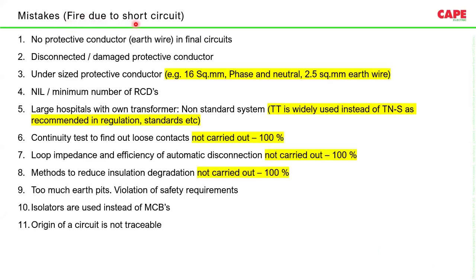Now, from the survey, the general findings we see are these. In a lot of cases there is no protective conductor, no earth wire in the final circuit. In the final circuit, in the sense, in the medical location, there are sockets available, but there is no earth wire on the socket. Most often the protective conductors are disconnected or damaged. Number 3 is an undersized protective conductor. That means the phase and neutral are 16 square mm, but the earth wire is only 2.5 square mm. This is actually a violation. Up to 16 square millimeters, phase, neutral, and earth must be the same size.